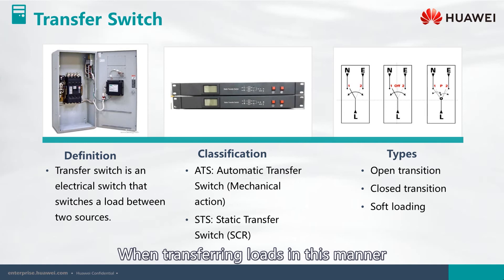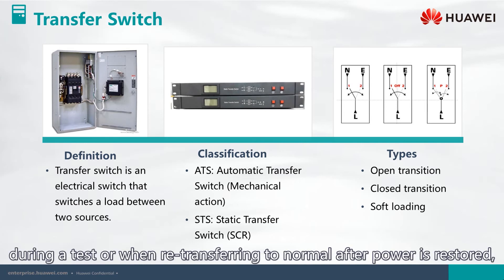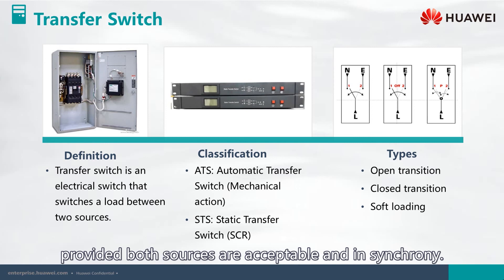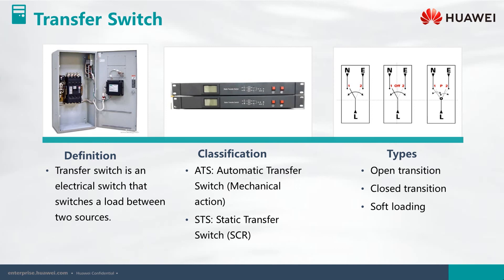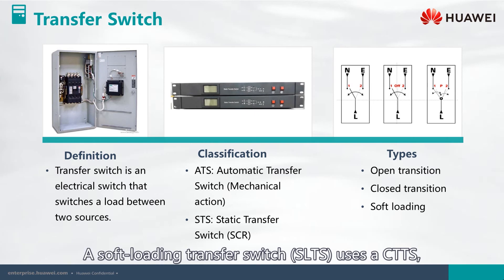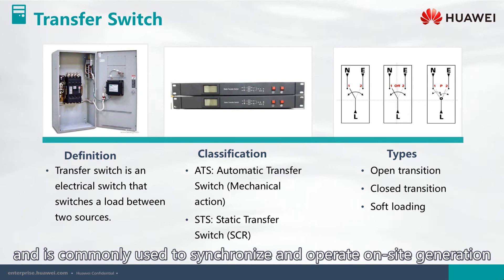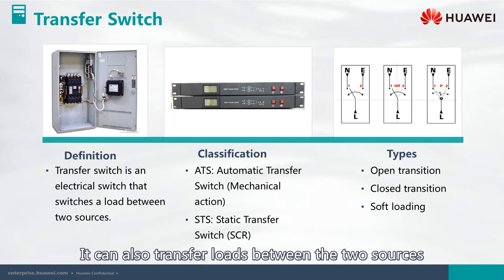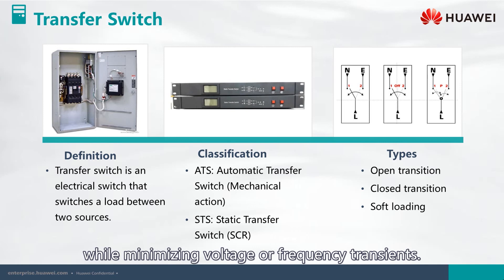When transferring loads during a test or re-transferring to normal after power is restored, the switch operates in make-before-break mode, provided both sources are acceptable and in synchrony. A soft loading transfer switch, SLTS, uses a CTTS and is commonly used to synchronize and operate on-site generation in parallel with utility power. It can also transfer loads between the two sources while minimizing voltage or frequency transients.